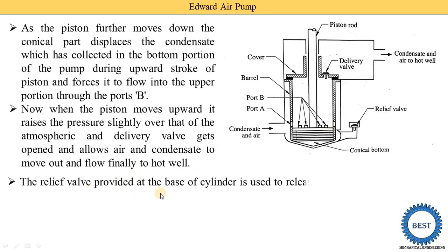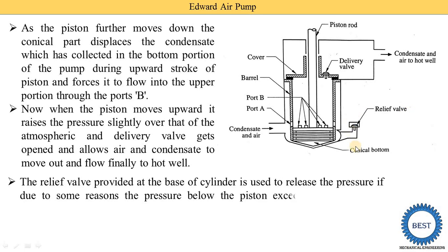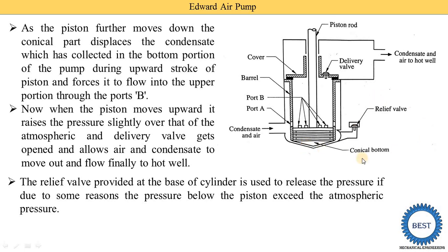A relief valve is provided at the base of the cylinder, as shown here. This relief valve is used to release pressure if, for some reason, the pressure below the piston exceeds atmospheric pressure. When the pressure of condensate and air below the piston rises above atmospheric pressure, this relief valve opens and releases the condensate and air to the atmosphere.